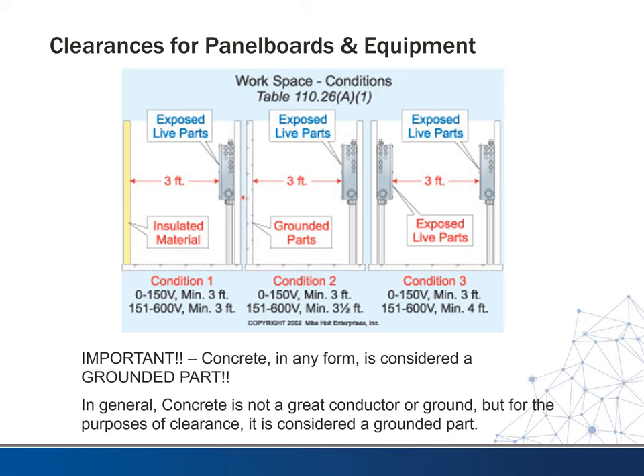Now, concrete is not a great conductor, but it technically will conduct electricity, especially depending on the amount of moisture that might be associated with it. So for National Electrical Code purposes, it falls in this condition too. So, just keep that in mind. The only time that might change things for you a little bit is if you're down in this 151 to 600 volt range, instead of 3 feet, you're going to need 3.5 feet clearance.